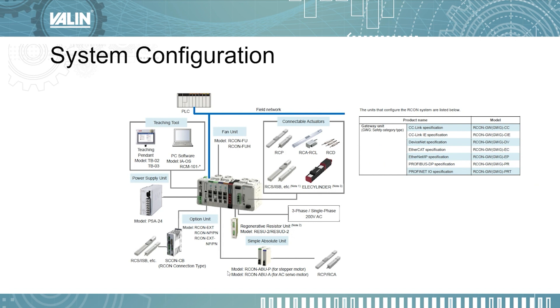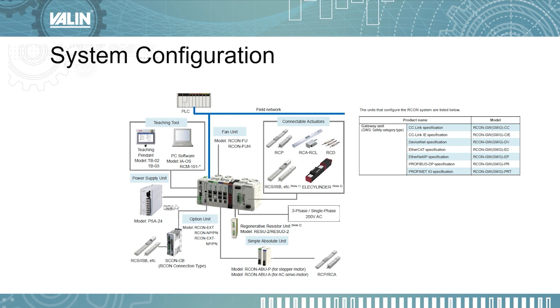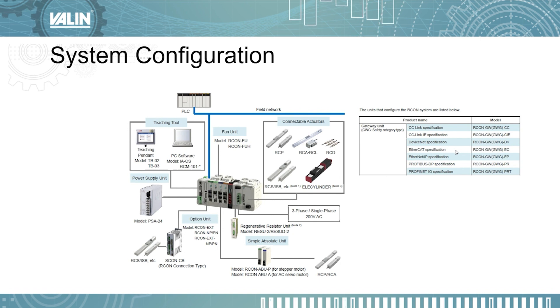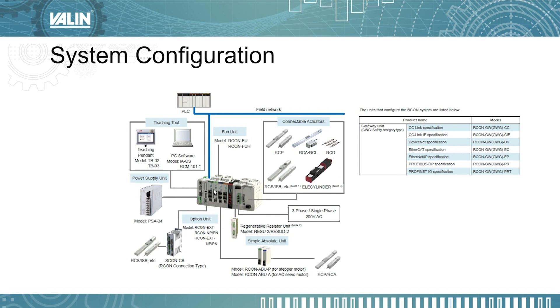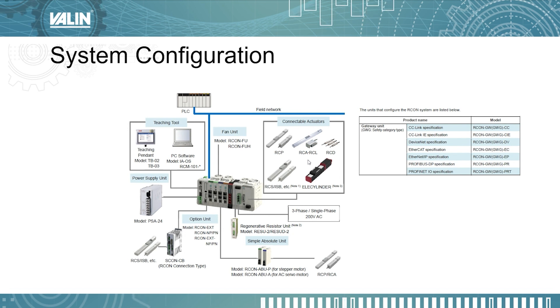Here is the system configuration you can have with the RCON controller. On the very left side is the gateway, with a 24V power supply connected to power it. The gateway can be CC-Link, DeviceNet, EtherCAT, Ethernet IP, Profibus, or ProfiNet. In our demonstration today we will use Ethernet IP. Next to it, you can stack up whatever drive you need for the actuator. The actuators can be RCP, RCA, RCL, RCD, RCS, ISB, as well as the electric cylinder EC cylinder.